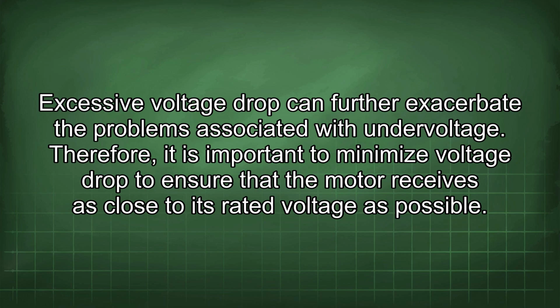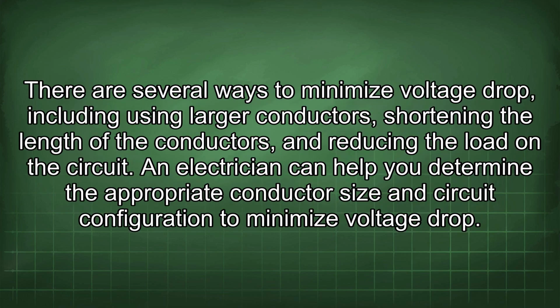Therefore, it is important to minimize voltage drop to ensure that the motor receives as close to its rated voltage as possible. There are several ways to minimize voltage drop, including using larger conductors, shortening the length of the conductors, and reducing the load in the circuit. An electrician can help you determine the appropriate conductor size and circuit configuration to minimize voltage drop.